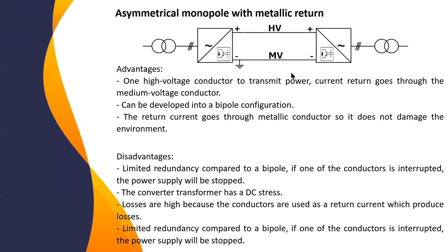For metallic return, there's no such disturbance problem because you use a medium voltage conductor for the return current, but at the end there's additional cost because you have to buy the medium voltage conductor, plus additional losses from it. So the difference is: with metallic return we have extra cost and losses from the medium voltage conductor, but with ground return we don't have that cable cost, though we need permission because the return current passing through metallic equipment or an AC substation can cause disturbance or corrosion, for instance to pipes.